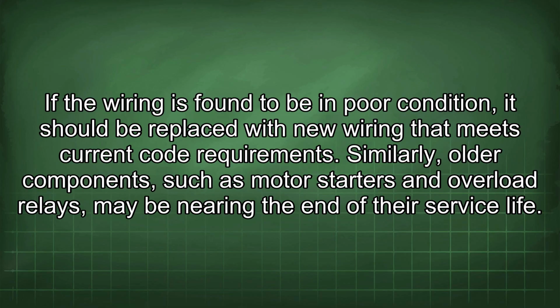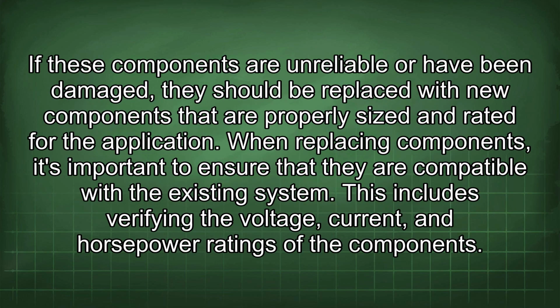If the wiring is found to be in poor condition, it should be replaced with new wiring that meets current code requirements. Similarly, older components such as motor starters and overload relays may be nearing the end of their service life. If these components are unreliable or have been damaged, they should be replaced with new components that are properly sized and rated for the application.